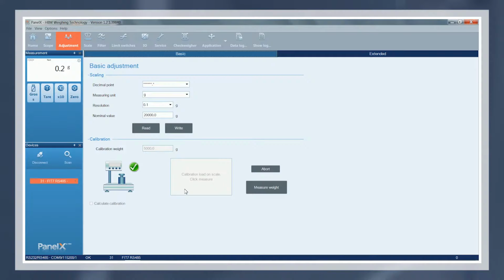We are then asked to click Measure Weight to communicate the measured value of the calibration weight to the sensor array. Following the instructions step by step, we can see that a value very close to the calibration weight is displayed in the Panel X weight indicator. The static calibration process is complete.